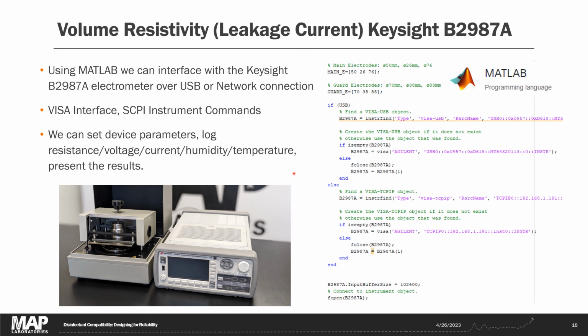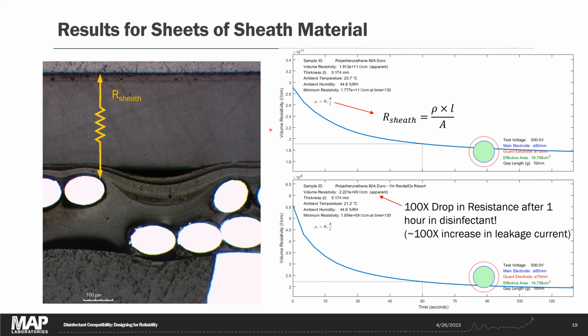You also need to be able to log the electrical resistance over at least 60 seconds of that applied 500 volts. In order to do that, we're issuing commands via SCPI instrument commands through MATLAB, having the instrument log the data, and then at the end of the test, MATLAB asks for the data from the instrument. It gets sent over the network, and MATLAB does all of our plotting for us. In this case, we used a thin sheet of the endoscope sheath material and measured the volume resistivity before and after an hour in our Revital-Ox Resert Disinfectant. We found that the volume resistivity decreased by 2 orders of magnitude after that 1 hour in disinfectant. That's 100 times increase in the amount of leakage current.